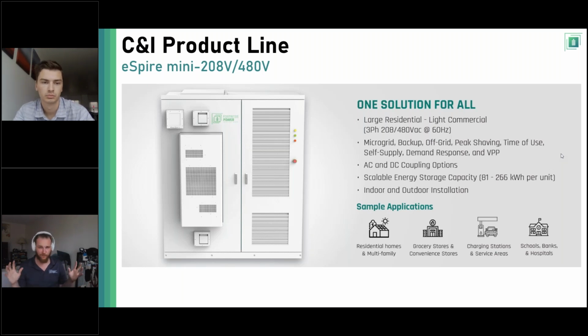The same exact microgrid controller and EMS software is in this system as in the larger system, so all the same applications apply. This is the same microgrid you'd get with the larger system, but in a smaller footprint, in one box. Another major difference between this system and the Espire 280 is that you can DC couple this one. There are actually DC-to-DC MPPTs inside this cabinet, and I'll show you in a sec what that looks like.